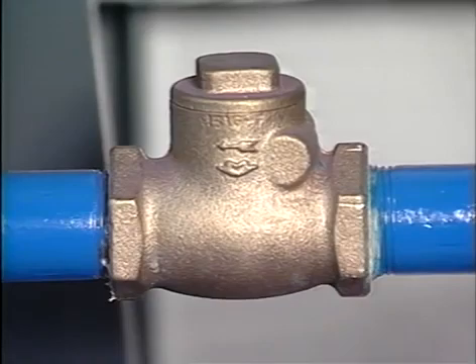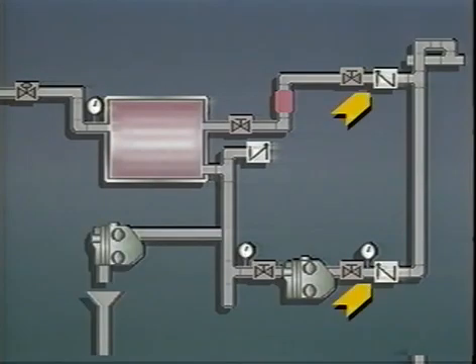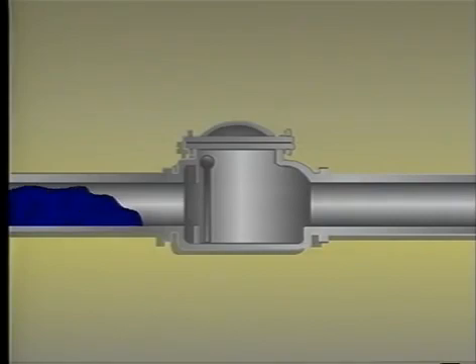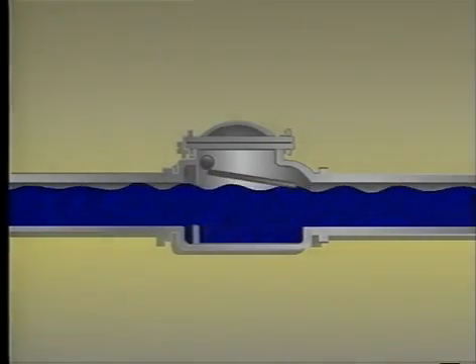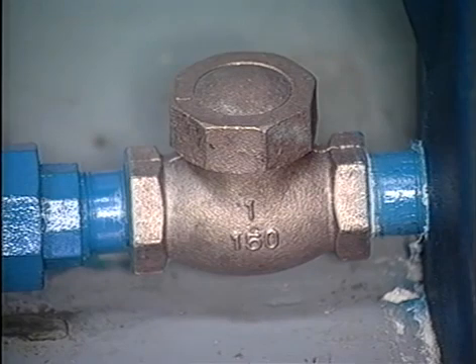Sometimes check valves can produce hydraulic shock. Swing check valves are often used to prevent liquid being drawn into spaces that are subject to intermittent vacuums. They are also applied to prevent backflow from elevated systems when adequate pressure to raise the liquid cannot be guaranteed. In either case, the acceleration of the reversing column of liquid may be quite high. If the swing length of the check valve is sufficient, the column will build enough inertia to cause hydraulic shock in the time it takes the valve to slam shut. Substitute silent or non-slam check valves for swing checks to prevent water hammer in these situations.